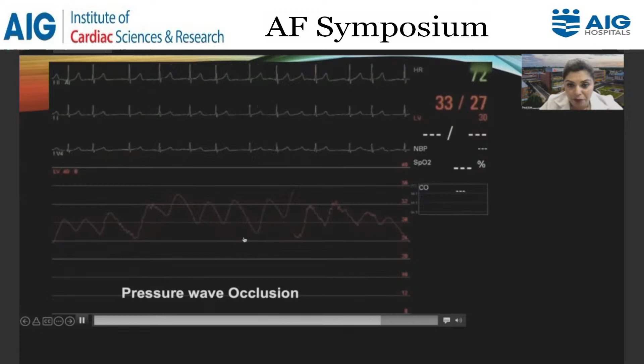So how do we show proximal seal? We'll start off with the A and the V wave. We will inflate the balloon. We will occlude it. And what you will see me do is pull the whole system back, show a leak on the pressure system. And then as we come on freeze, we move forward. Because as the Medtronic balloon comes on freeze, it actually gets a little bit bigger, and we don't want it to kind of push up.